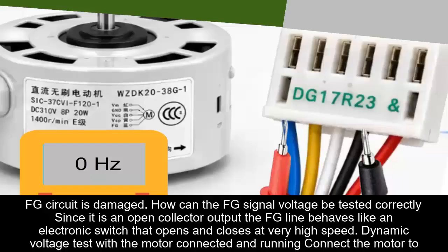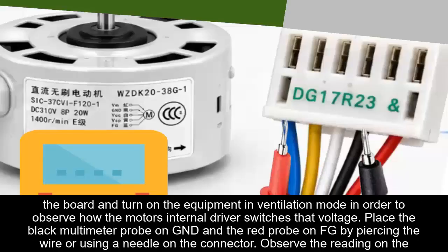How can the FG signal voltage be tested correctly? Since it is an open collector output, the FG line behaves like an electronic switch that opens and closes at very high speed. Dynamic voltage test with the motor connected and running. Connect the motor to the board and turn on the equipment in ventilation mode in order to observe how the motor's internal driver switches that voltage. Place the black multimeter probe on GND and the red probe on FG by piercing the wire or using a needle on the connector. Observe the reading on the multimeter display.